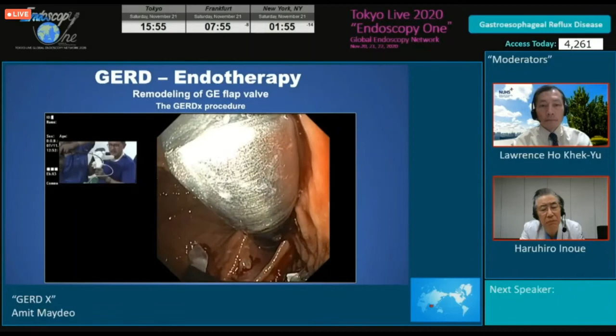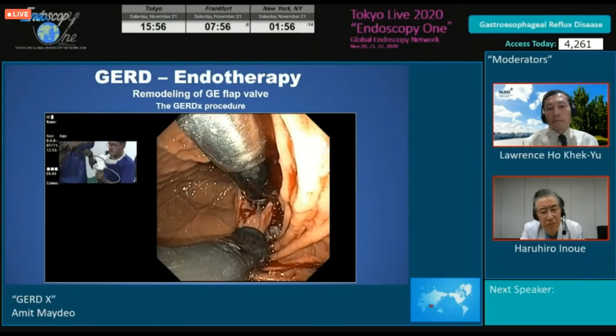At this time, I gently rotate the shaft of the GERDx, pull it a little backward so as to bring more tissue, and then close the arms. Once we know that the arms are closed in a proper fashion and the plication is the right location, then I bring it to the firing position and I fire the staple. After firing, the first thing to do is to release the helix by rotating it in an anti-clockwise direction. And then I open the arms.